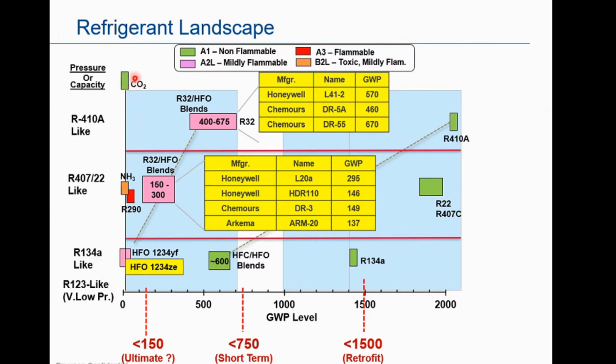Even from the reliability point of view, it's relatively dangerous compared to the refrigerant that we use today. So people in the developed countries are trying to use this refrigerant in the secondary loop, but the moment you use it in the secondary loop, the efficiency goes down, right? For example, ammonia is toxic in nature, so you can't use ammonia within the municipal limits of any city. So it has some disadvantages in terms of its properties. R290 is extremely flammable. You can't use it beyond a certain charge limit in air conditioning applications. There are some instances in India where R290 is getting used in room air conditioners, but not beyond that, because of the limitation on the refrigerant charge limit of R290 in air conditioning systems, right?